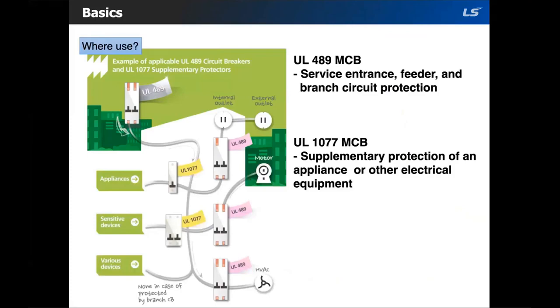So there are two types of MCBs, UL489 and UL1077. Let's look at the difference between those two, and how they distinguish the UL standard. The UL489 is a branch circuit protector. It has gone through way more rigorous testing compared to the 1077 to ensure that it will function as intended multiple times without failure. These can protect multiple devices and circuits. They can be used both as a branch and supplementary protector. Common applications include branch circuit protection in control panels, panel boards, switchboards, and motor control centers.